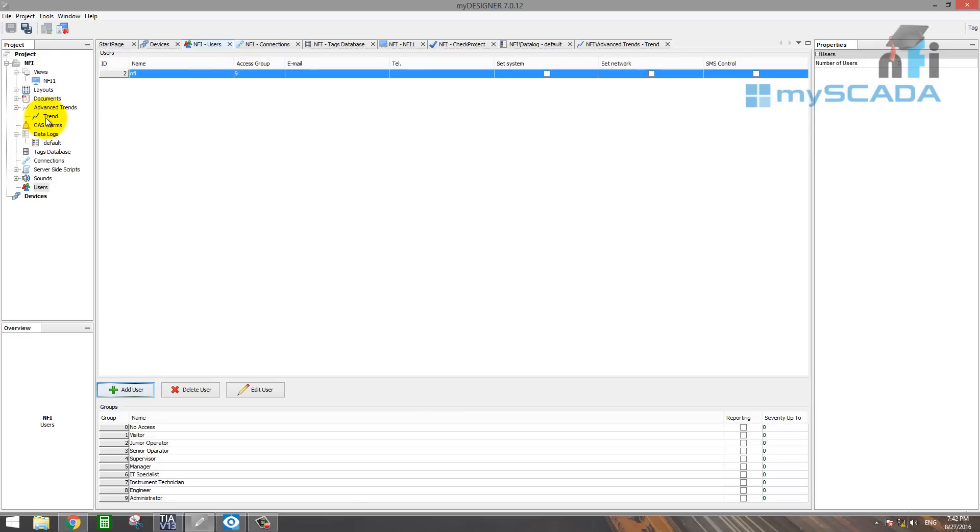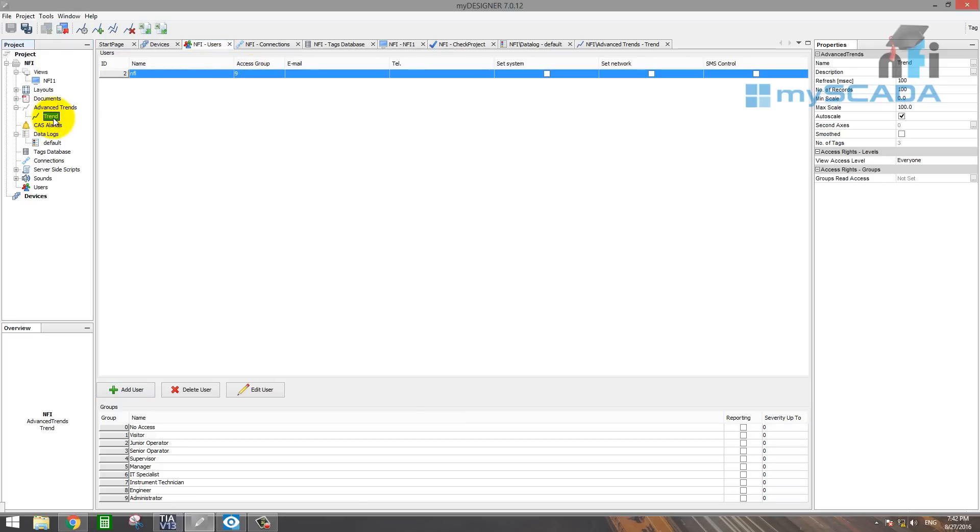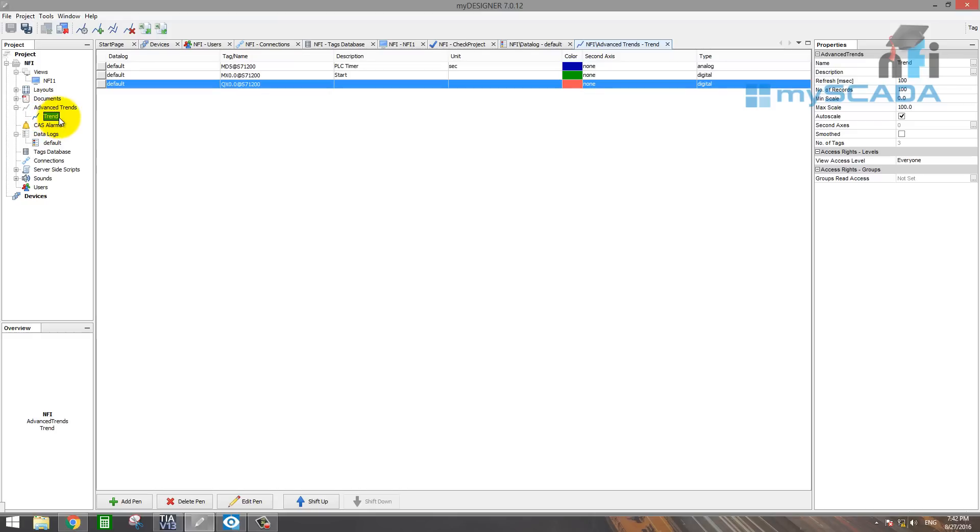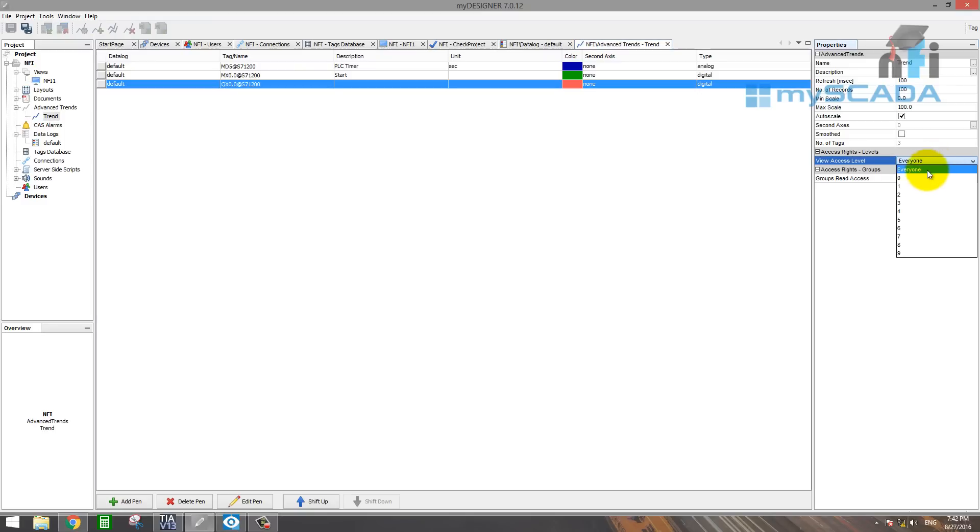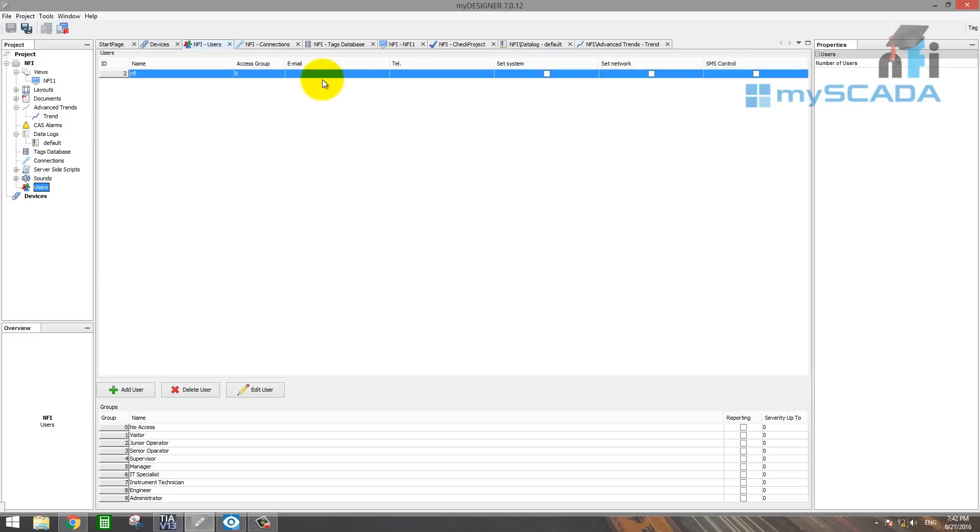So go back to trend. And now this trend has to be configured with authorization. So you will see here view access level. Who should access this trend? Select that to administrator nine. Now this is to nine. So only people who have the administrator level of nine can only view this.